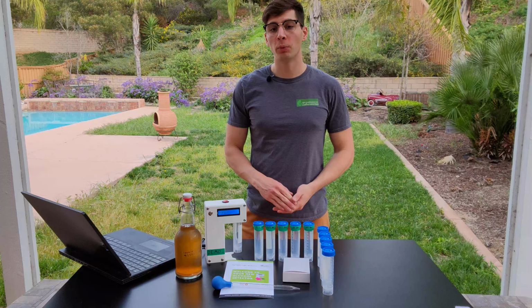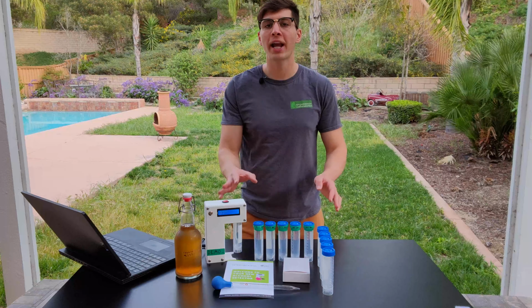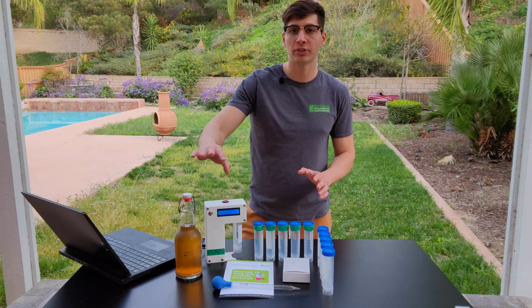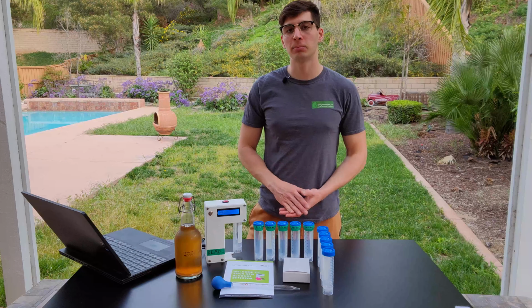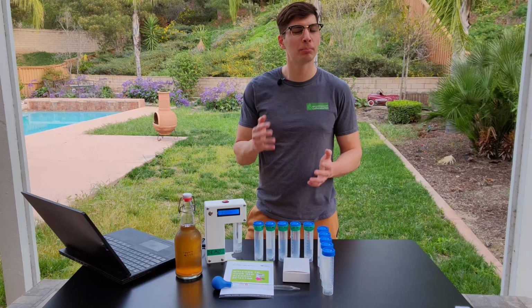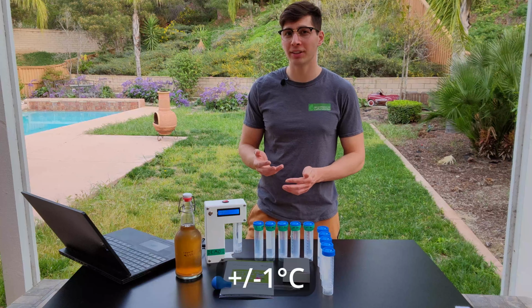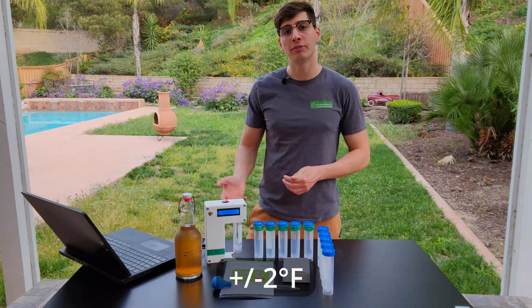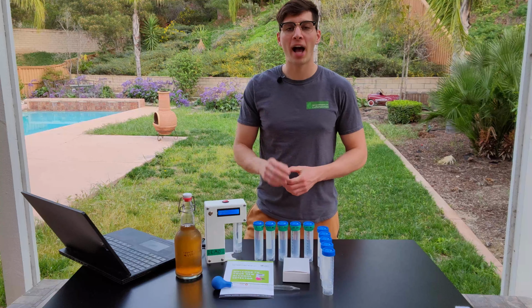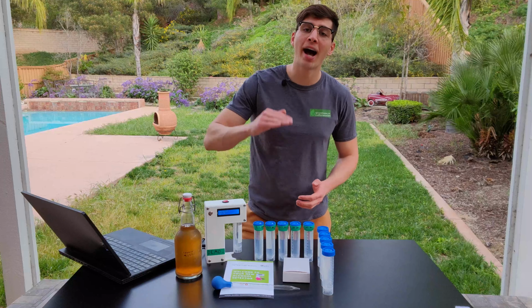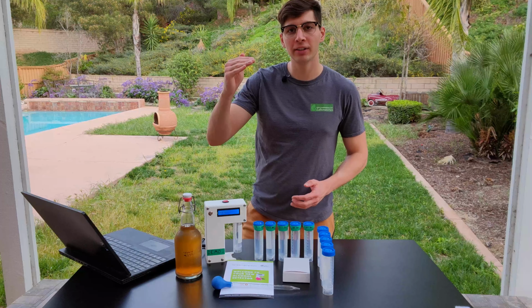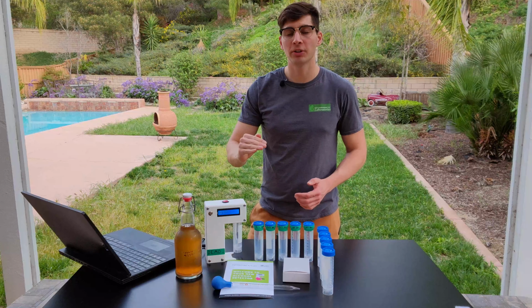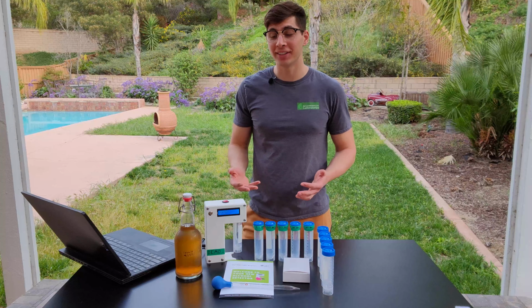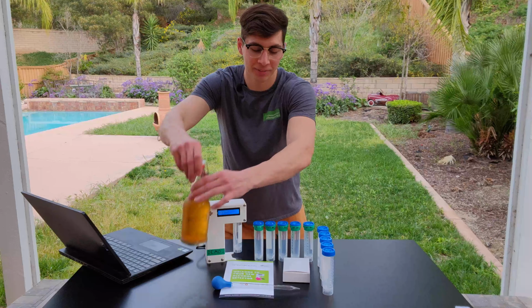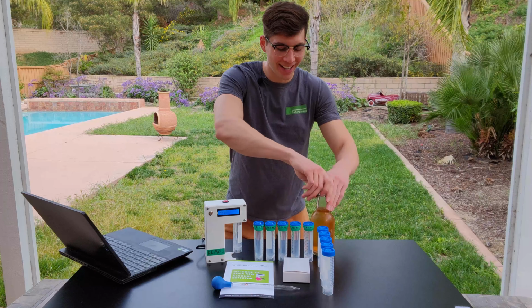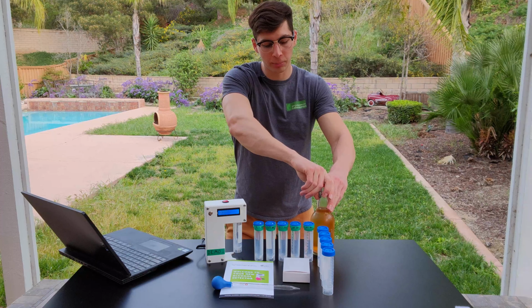Another important thing to note when using this device is that all of your calibration standards and all of your samples must be at the same temperature. When I say that, I mean plus or minus about 1 degree Celsius or plus or minus about 2 degrees Fahrenheit would be most accurate. If you read a sample at a higher temperature, you'll get a higher reading. If you read a sample at a lower temperature, you'll get a lower reading. So with that being said, I think it's a good idea to open this away from the computer and get it up to room temperature.